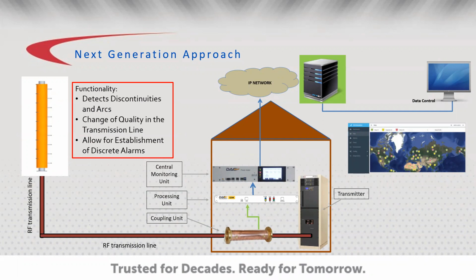The system can detect changes in return loss of less than -45 dB and with a localization accuracy of plus or minus 18 inches. And the system does meet or exceed the FCC out-of-band emission standard of less than -110 dB on carrier. And the system can also detect sustained arcs greater than 100 microseconds.